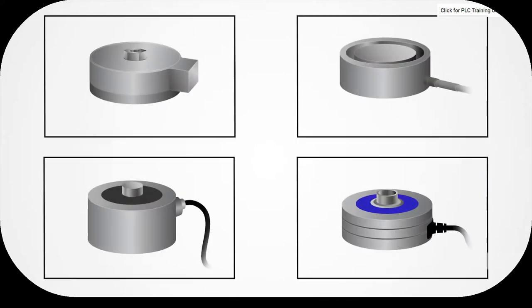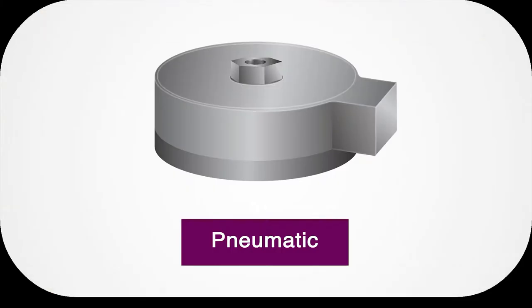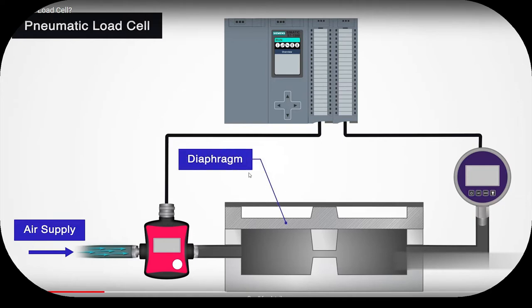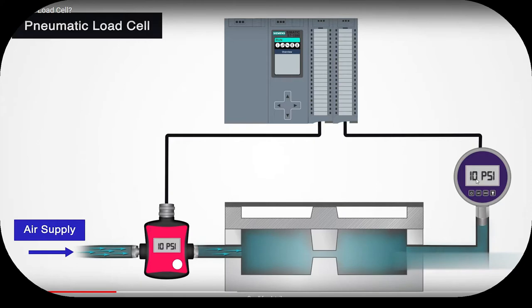There are four common types of load cells: pneumatic, hydraulic, strain gauge, and capacitance. A pneumatic load cell consists of an elastic diaphragm attached to a platform surface where the weight will be measured. There is an air regulator limiting the flow of air pressure and a pressure gauge. When an object is placed on a pneumatic load cell, it uses pressurized air or gas to balance out the weight of the object.